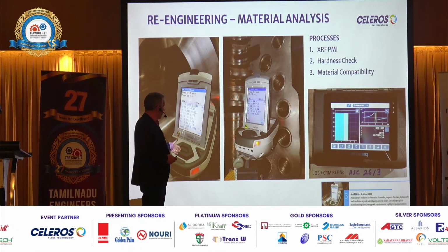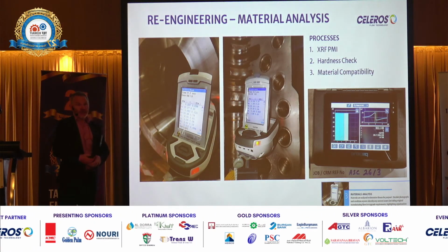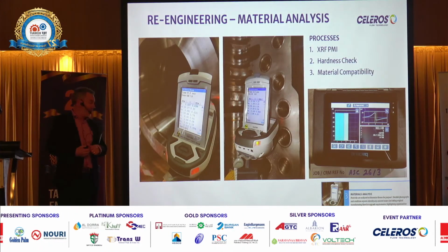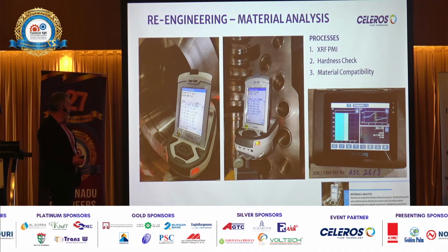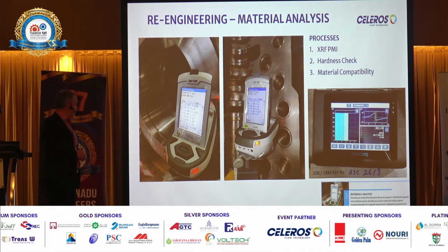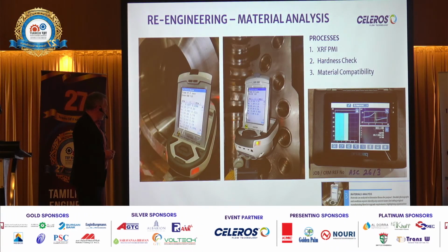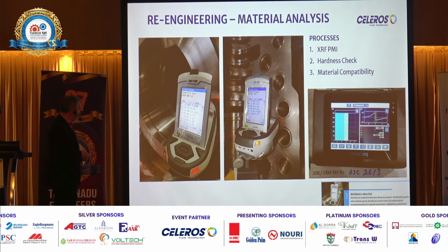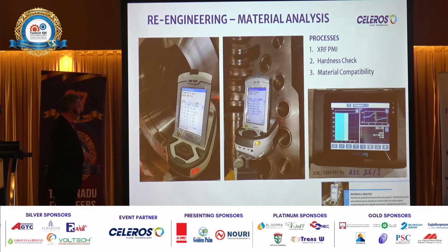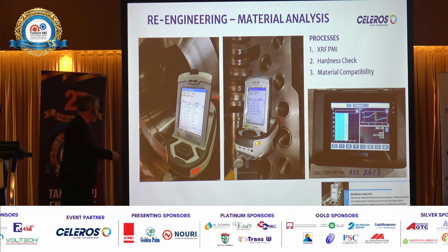Right, PMI, positive material identification. We've got all the tools. Sometimes we get the pump data sheet, and that's fine, it'll tell us what the materials are. Other times it's obsolete equipment, we don't have any information on it, so we'll use our PMI instruments to get a positive identification on the material.